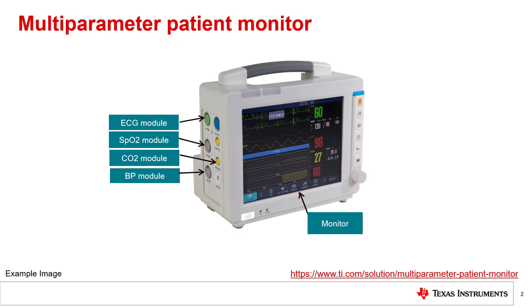Here is an example of a patient monitor with different connectors where all these different cables get connected. These type of patient monitors are bedside or classic patient monitors, which are seen in hospitals and clinics. There is also a trend of moving towards portable patient monitors, which are small units that can be worn on the waist. The challenges for these portable patient monitors are not only size but also quiescent current, efficiency, and thermal performance.